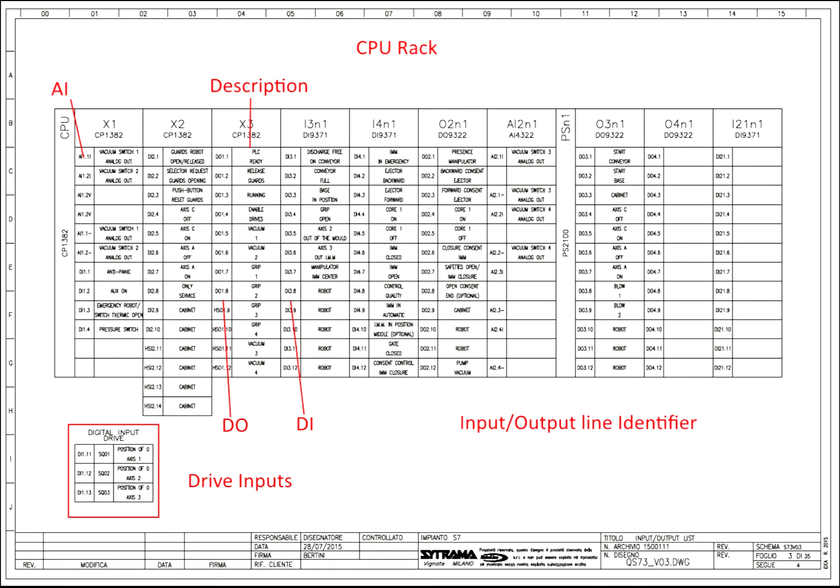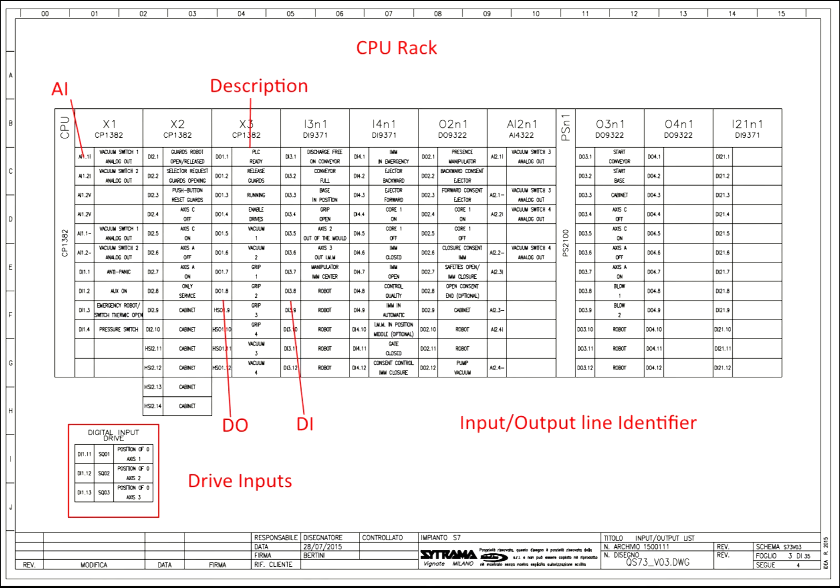Okay on the next page we have the CPU rack. The CPU rack is laid out to show you if it's a DO or a digital output. It shows you a DI which is a digital input. The AI is an analog. Notice our analog circuits are the first things in our rack. And then each one of them has a description. It gives you a description of what that input or output is.